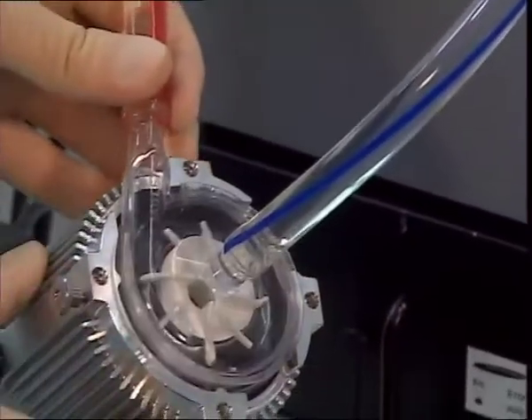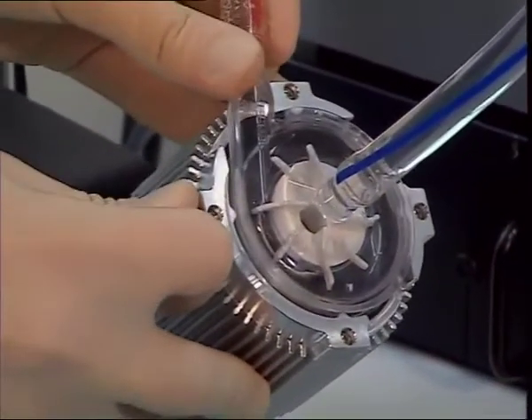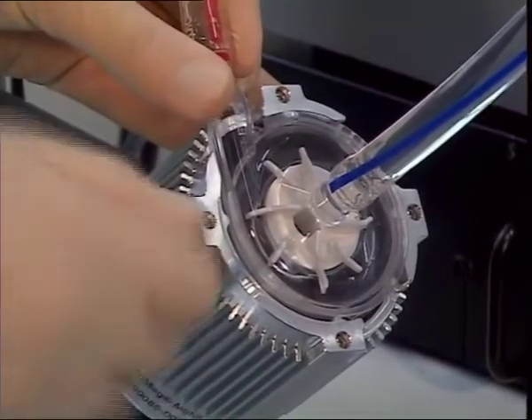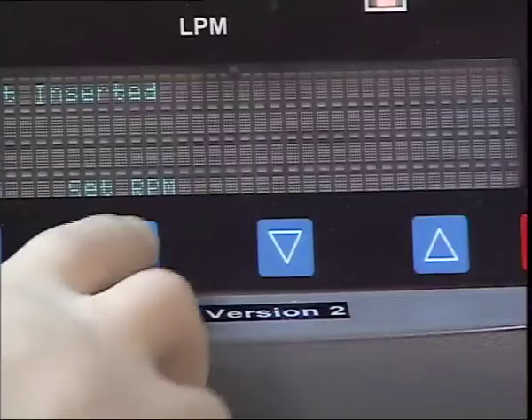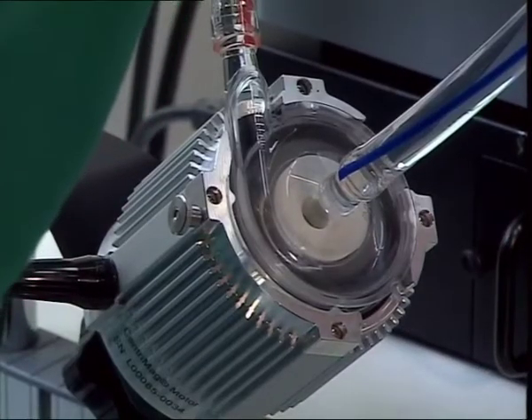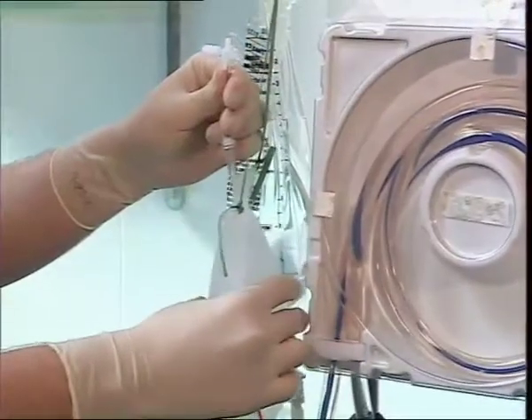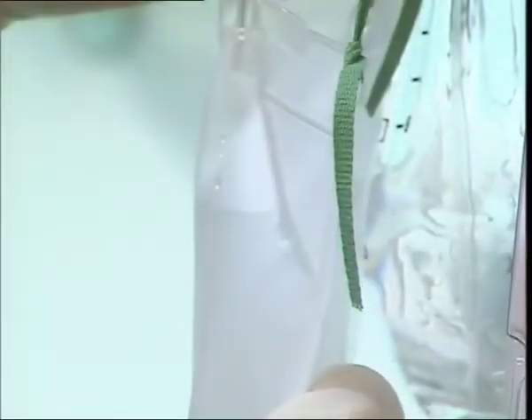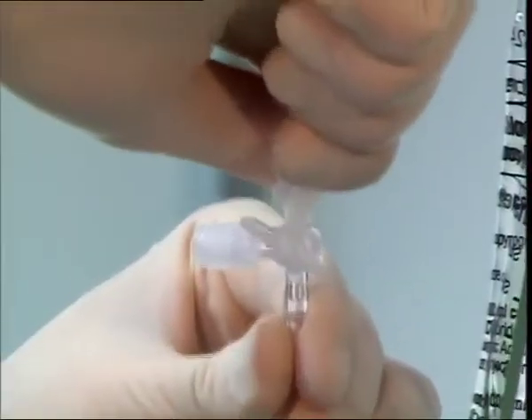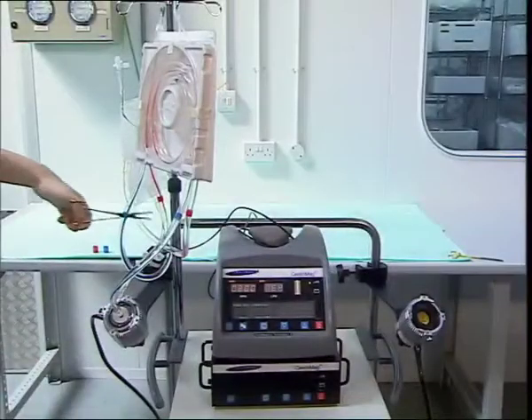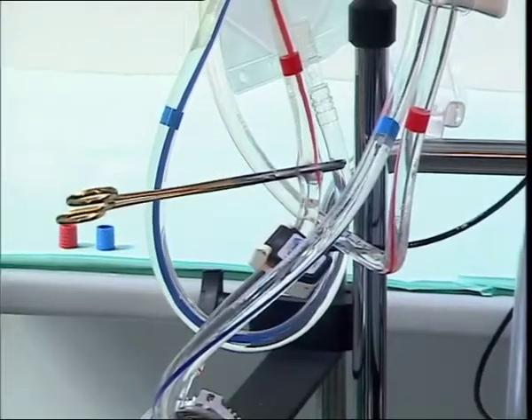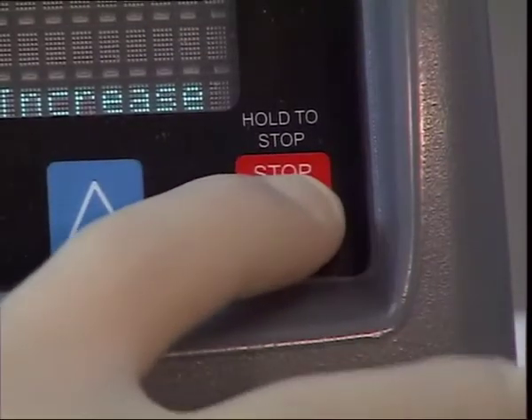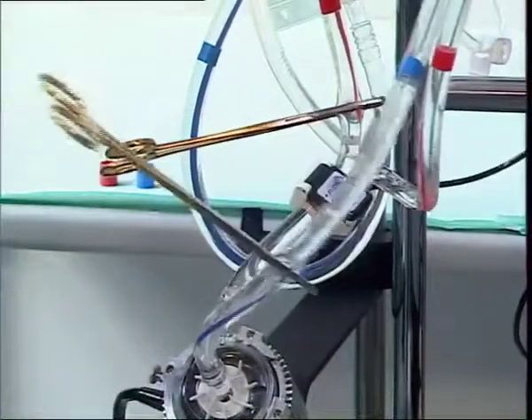Do not hit the pump hard or with metal objects at any point. Reattach and restart the pump head and perform a final check for any air. Any remaining air in the recirculation bag can now be removed to prevent air entrainment. Finally, with the pump running, clamp the red outlet tubing, switch the pump off and clamp the blue inlet tubing.